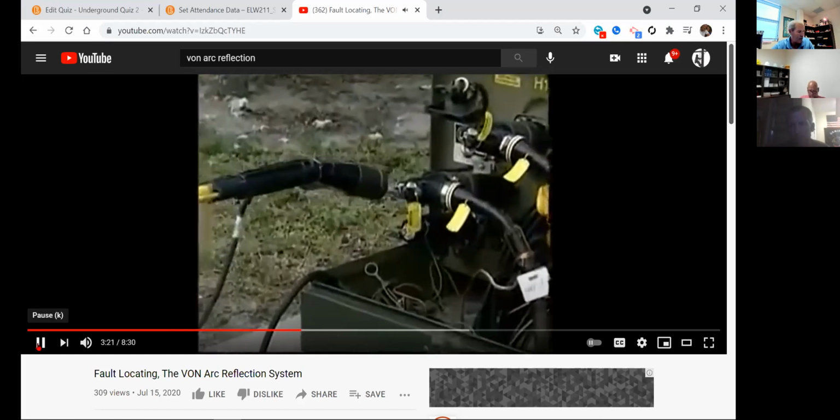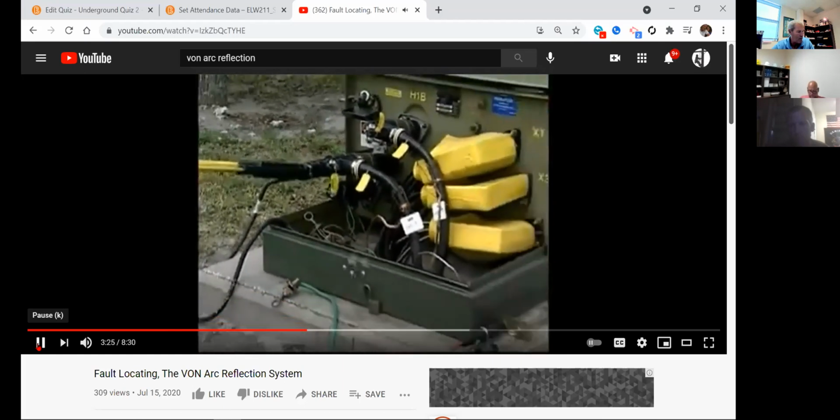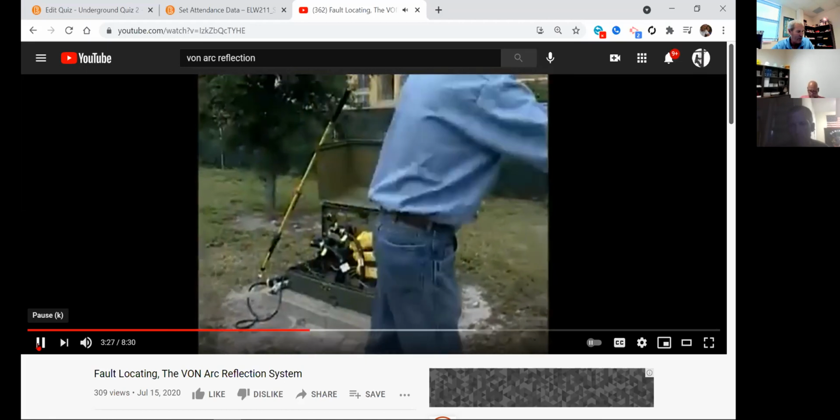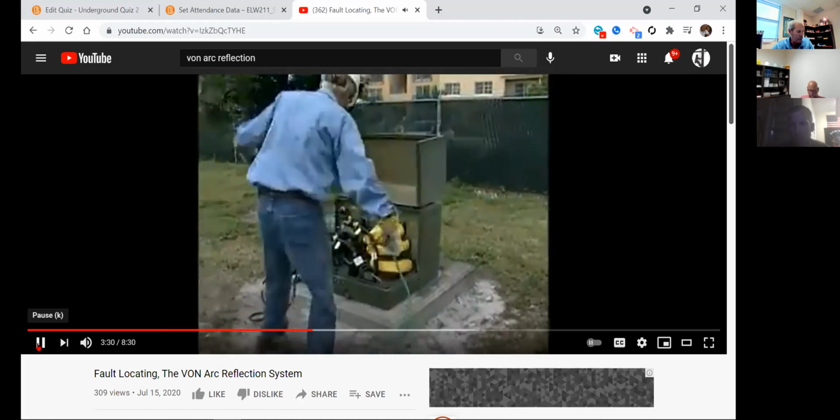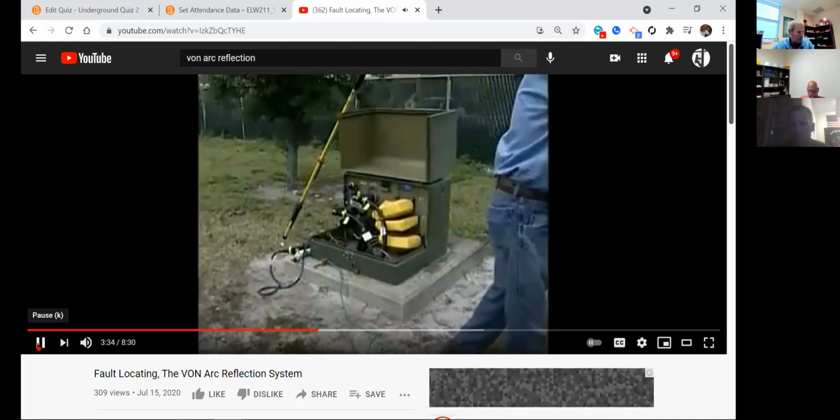After you complete the testing, be sure to insert a grounding elbow in the feed-through. You're now ready to hook up the leads from the VON. One quick note, be sure the green safety case ground is uncoiled fully before beginning the hookup.